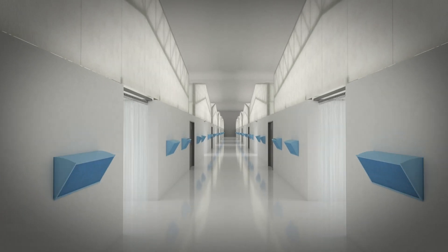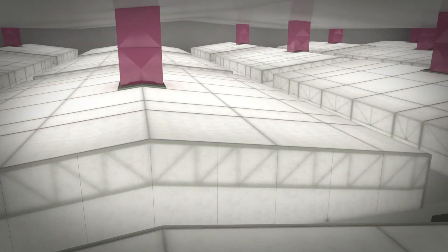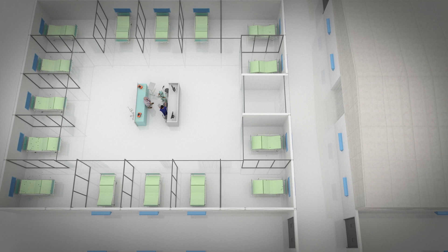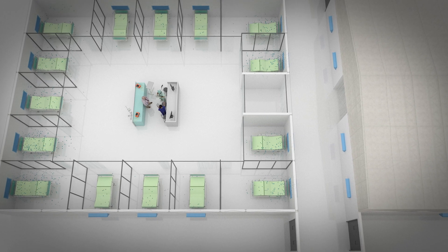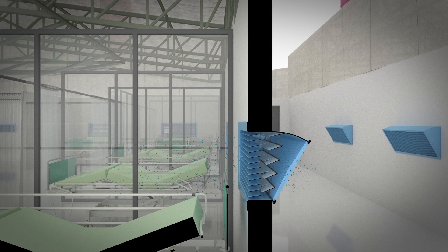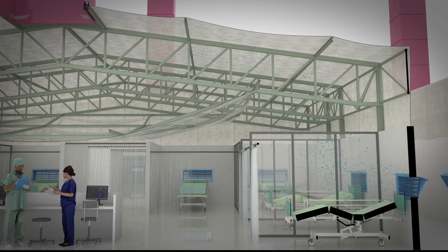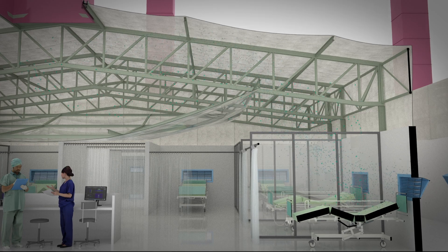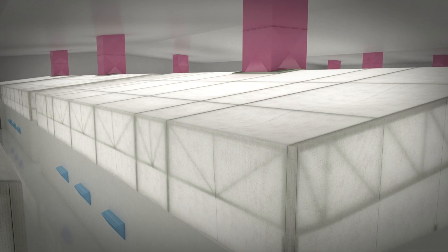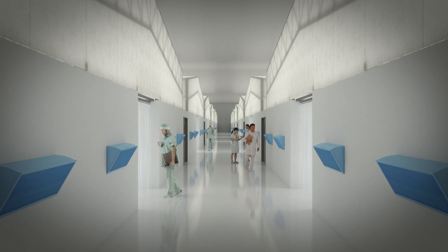This alternative version, reversing air flows, is proposed for a typical ward in more humid warm coastal climates, and is potentially entirely naturally ventilated. It draws air into the ward at low level behind each bed head through a simple non-return flap, and as it warms, rising to be exhausted using a natural stack effect generated by a central stack — a chimney in effect — puncturing the roof above the centre of each ward. Entry into each ward is directly from the outside, and the corridor spaces around the wards are all clean and strictly isolated by airlock lobbies.